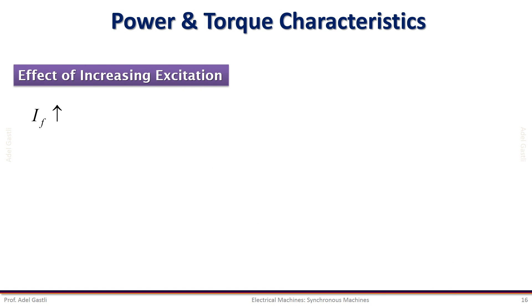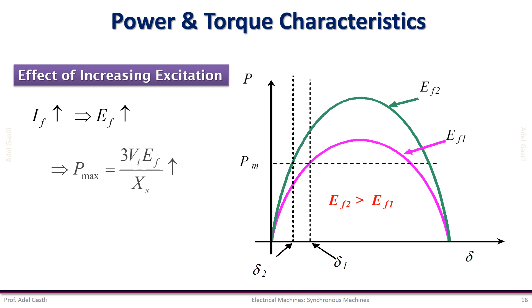By increasing the excitation current from IF1 to IF2, the excitation voltage increases from EF1 to EF2 as shown in this graph. So the maximum power that can be delivered by the machine increases, and the pull-out torque also increases. If the load real power is unchanged and equal to PM, the power angle decreases from delta1 to delta2, which means that for constant power delivery, if we increase the excitation the power angle will decrease to keep the same power.